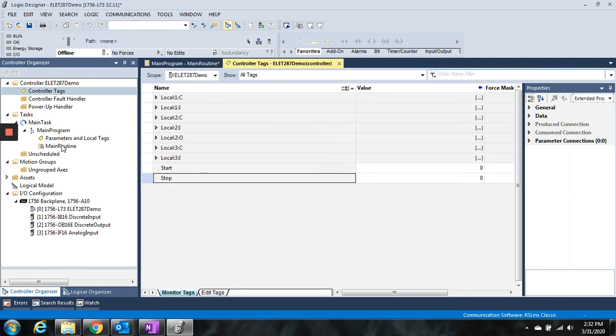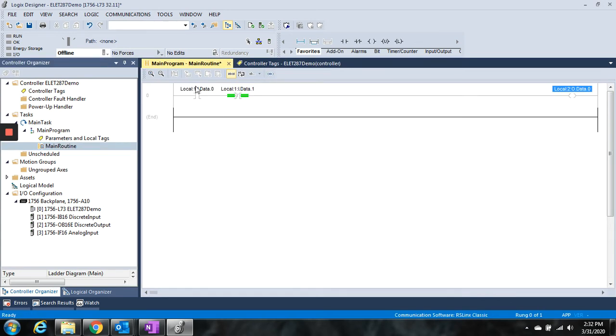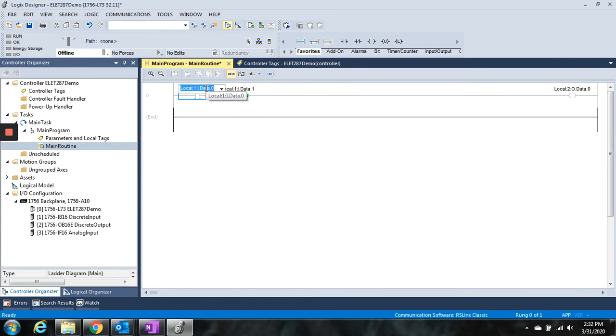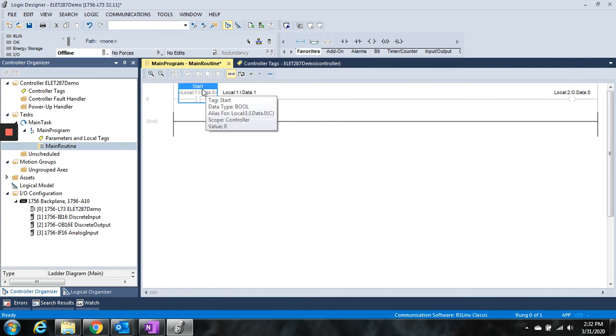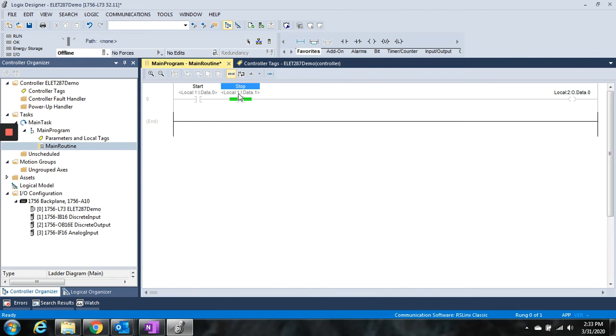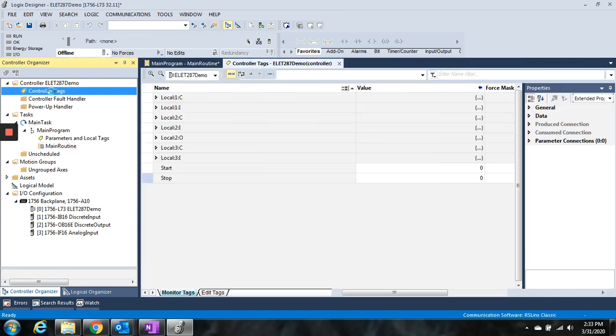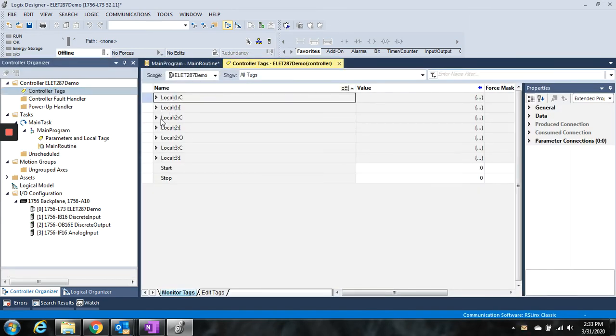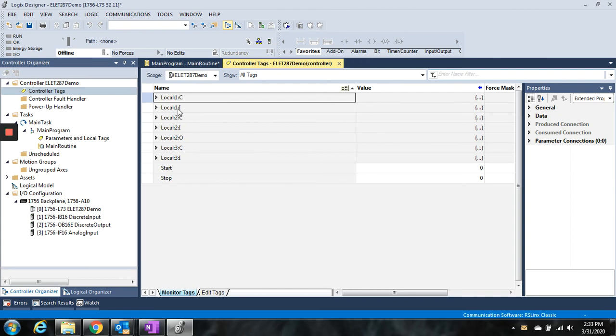So I had to go to edit tags down here, and I'm going to go back to monitor tags. So these two are now being created. If I were to come back to the main routine, they don't quite show here yet. But if I were to say start now, you'll see that it's mapped to local 1:I data 0. And if I say stop, I type in the tag name stop, it is now mapped to local 1:I data dot 1. So we don't have to necessarily deal with these tags always, but we can create alias tags and point them back to those. We can create alias tags for anything. So I can even create another alias tag that points to this alias tag, which is in turn pointing it back to the local 1:I dot 0.